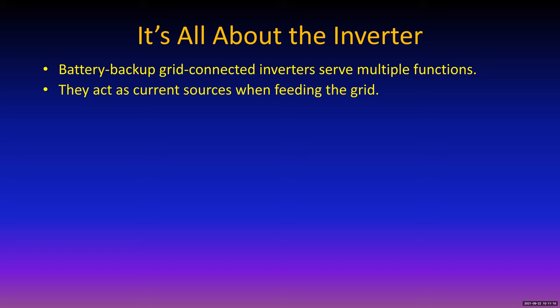But if you have a current source, it merely monitors the phase of the voltage on the grid and injects current in phase with the voltage on the grid—unless, of course, the utility says, 'we wish you could give us some current at a leading power factor so you can help us correct our power factor, then maybe we can eliminate the need for some capacitors for power factor correction.' So the utility can actually ask your inverter, without your intervention, to please provide some current with a leading power factor.